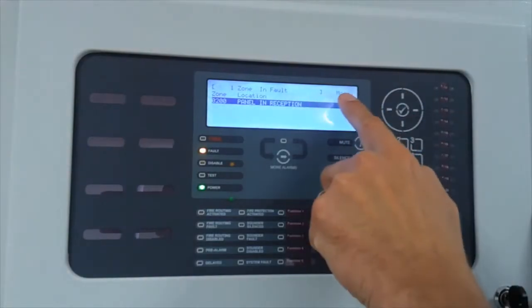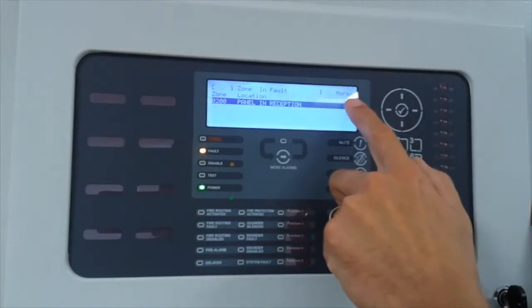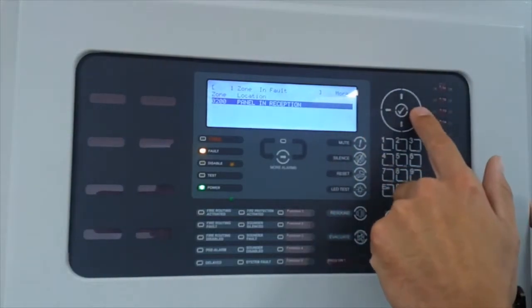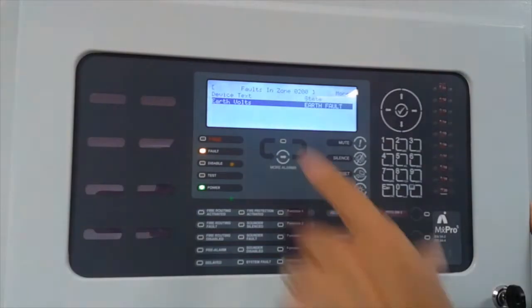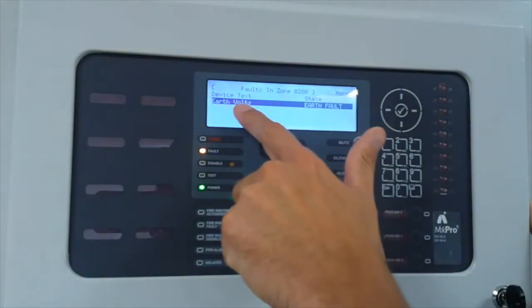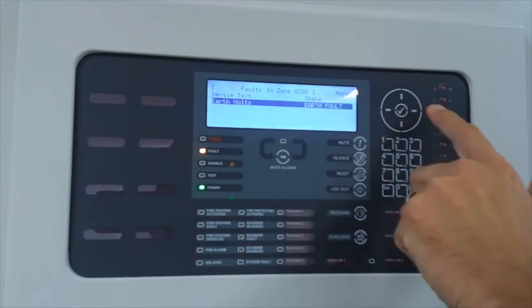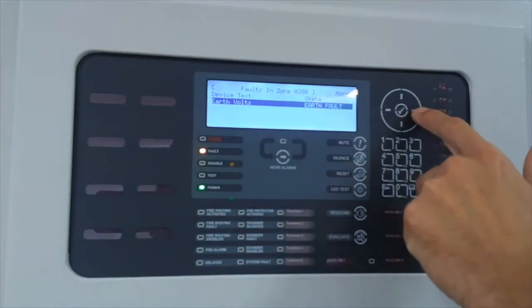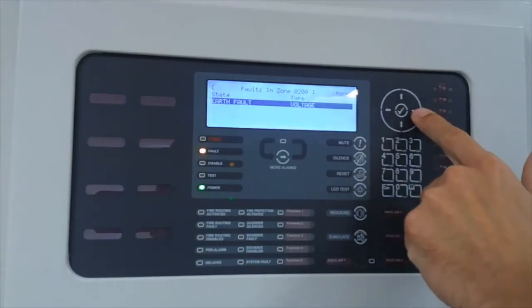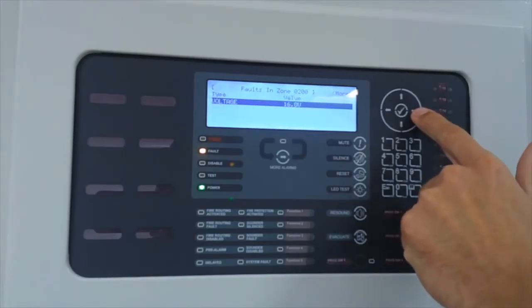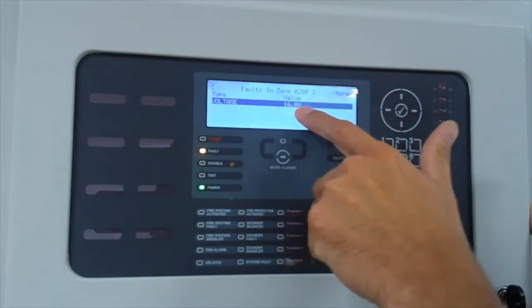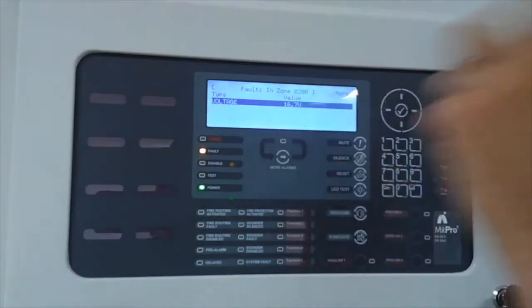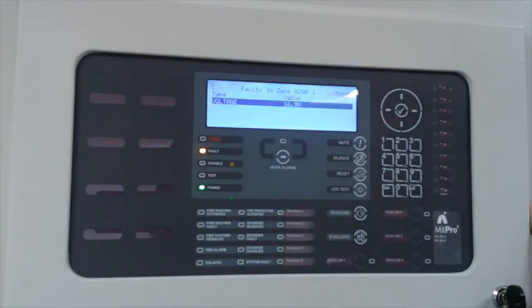Scroll to the right-hand side for further information. We can see the device text earth faults, the state is an earth fault. The voltage is the measurement type and we can see our voltage measurement is 16.8 volts.